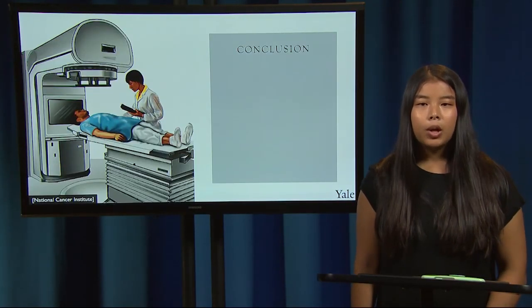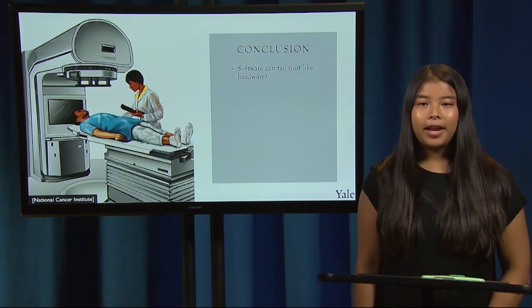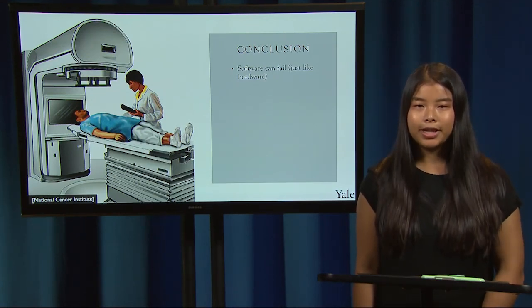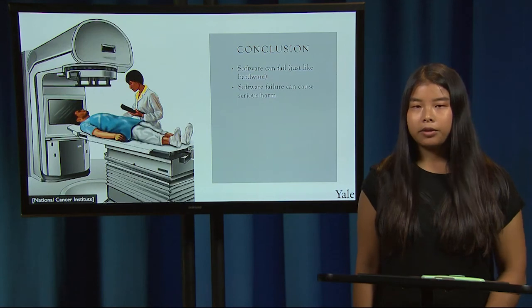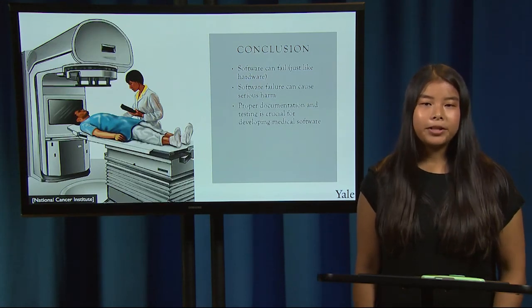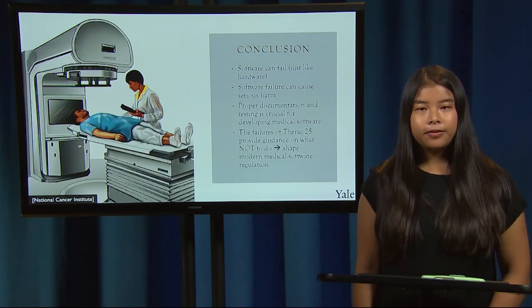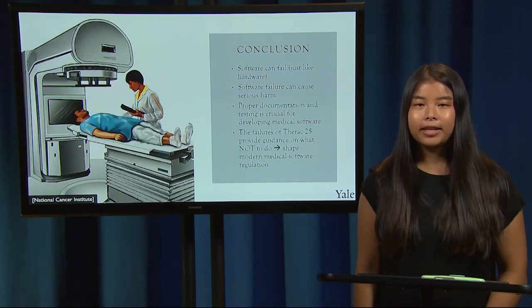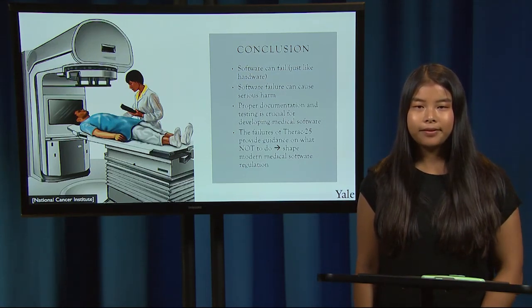Since these incidents, the FDA has taken a much more cautious approach in approving software. They now highly emphasize proper documentation and testing. In conclusion, we learned that software can fail, just like hardware. In many cases, it is hard to detect where and how it will fail, because this requires very thoughtful testing. Software failure, just like hardware failure, can cause serious harm as seen by the six reported patient incidents. Proper documentation and testing is crucial for developing medical software. Finally, the failures of Therac 25 provide guidance on what not to do, thus shaping modern medical software regulation through agencies such as the FDA. Thank you.